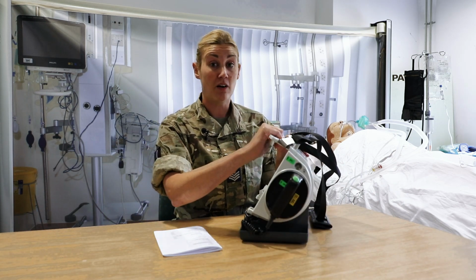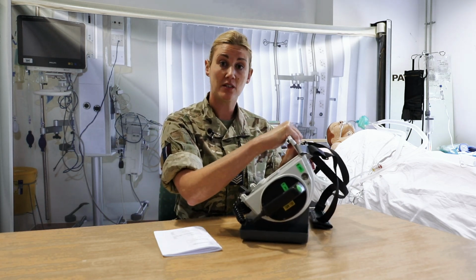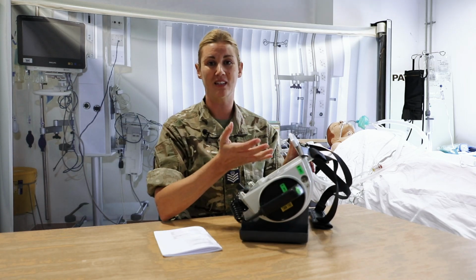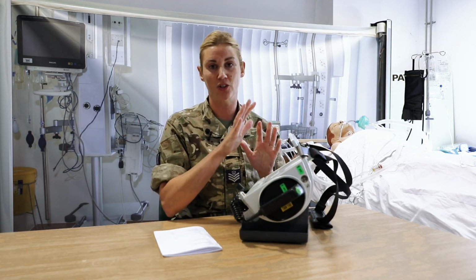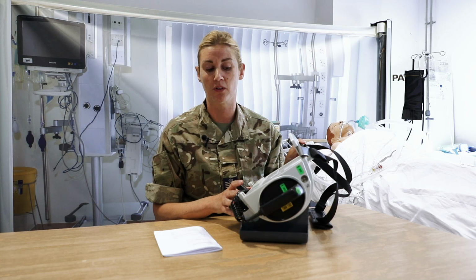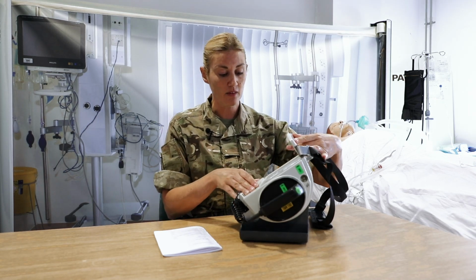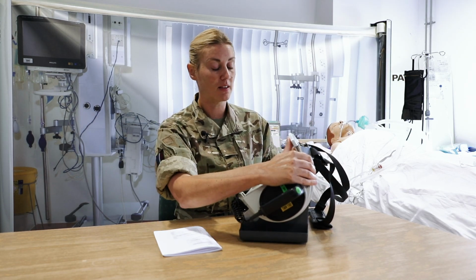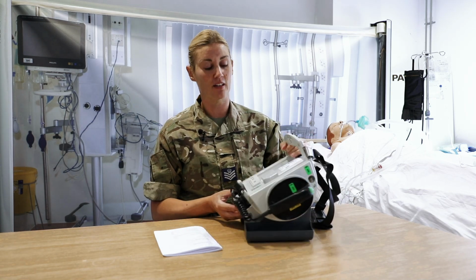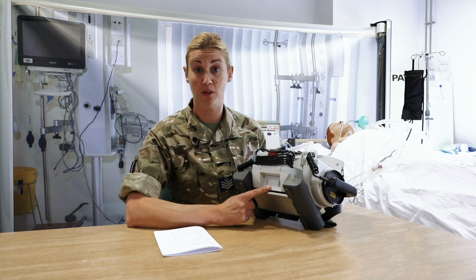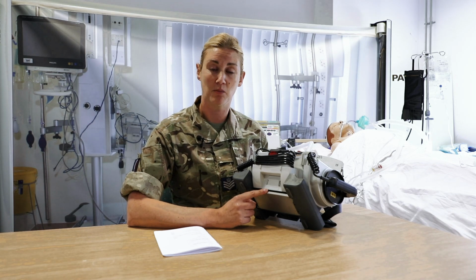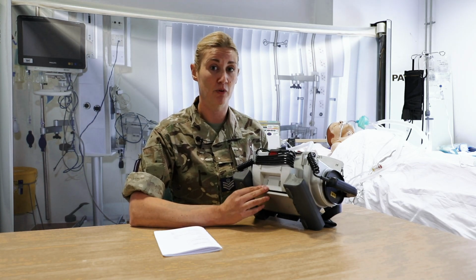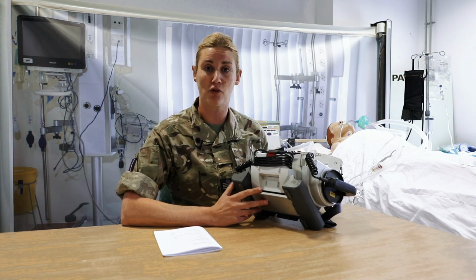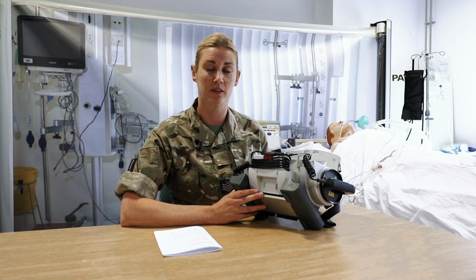The defib itself has a tilt mechanism, so you just push it back. What this is for is that when it's all connected, it just gives you a slightly different angle to view the monitor if you need to. Again, there is a battery in this, and the tilt function gives you a view of the battery, which is at the base. And in the same way as the monitor, there's no need to routinely remove these if there isn't any evidence of cracking or leakage of battery fluid.